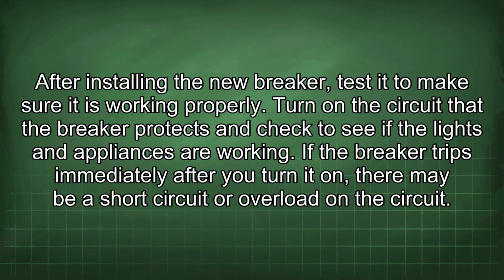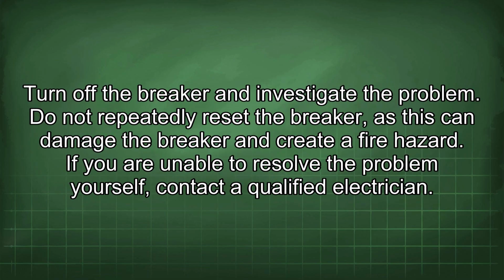After installing the new breaker, test it to make sure it is working properly. Turn on the circuit that the breaker protects and check to see if the lights and appliances are working. If the breaker trips immediately after you turn it on, there may be a short circuit or overload in the circuit. Turn off the breaker and investigate the problem. Do not repeatedly reset the breaker, as this can damage the breaker and create a fire hazard. If you are unable to resolve the problem yourself, contact a qualified electrician.